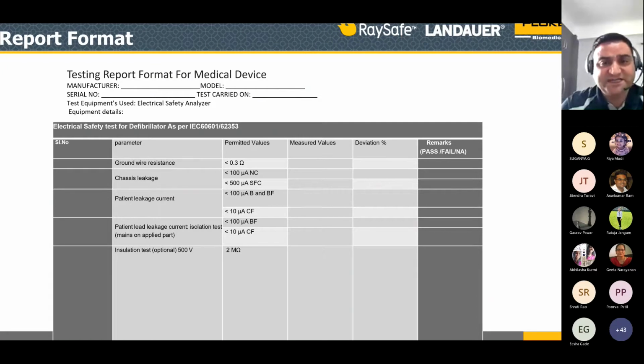Again, same as I said, if you have patient leakage currents, again, B and BF type, as I mentioned earlier, those are the equipments depending upon the body parts. So less than 10 microamperes for CF and patient leakage current isolation test less than 100. This is the criteria which you will find in IEC 60601 and 62353. Those are the permissible limits. You can refer to those limits anytime. Then measured values, and what is the deviation? Remarks, whether it is pass or fail, you have to give that report.